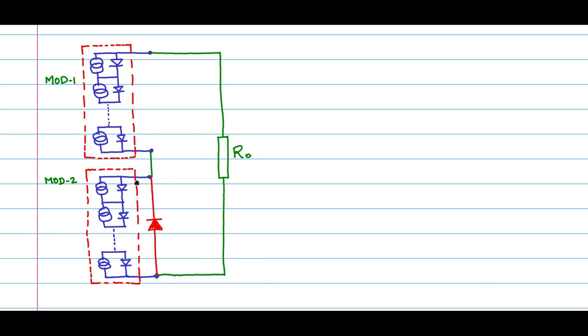We don't know which of the modules are having shading, so therefore you have to put this kind of protection bypass diode to every module which is there in the circuit. So you should also put a protection diode across module 1, as you see here.